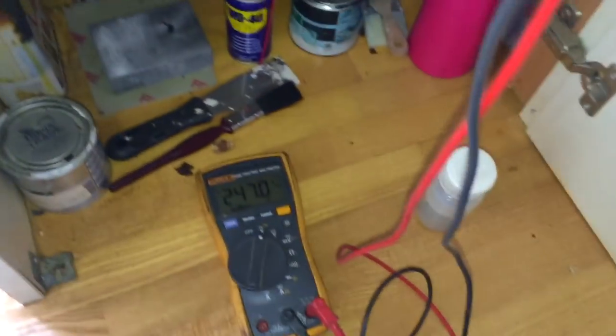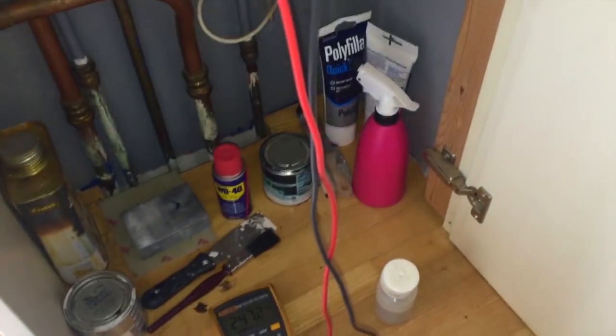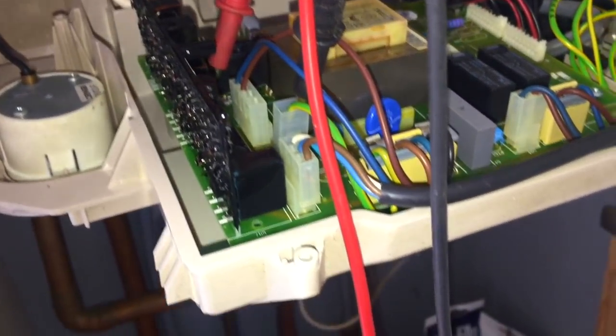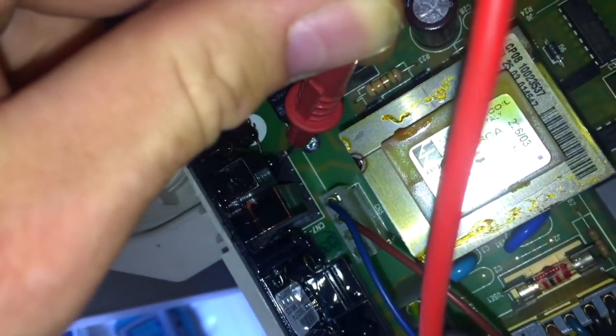Okay, so I was just packing up to go, and the boiler did the same thing again. Thought it was fixed, it's obviously not. So what I'm doing, I'm actually testing power from the main board to the ignition board, because when it did the fault, I'm sure I could hear the air pressure switch click. So if the air pressure switch made, the next step is that this little board, the ignition board, gets 240 volts. Now, unlike the one earlier, there's no pins to test, so I'm testing that tiny little bit of metal down there.